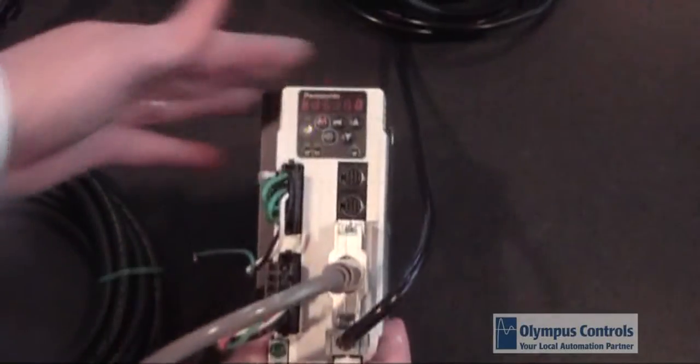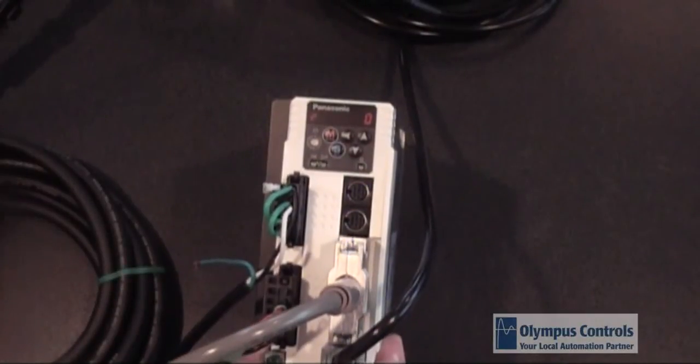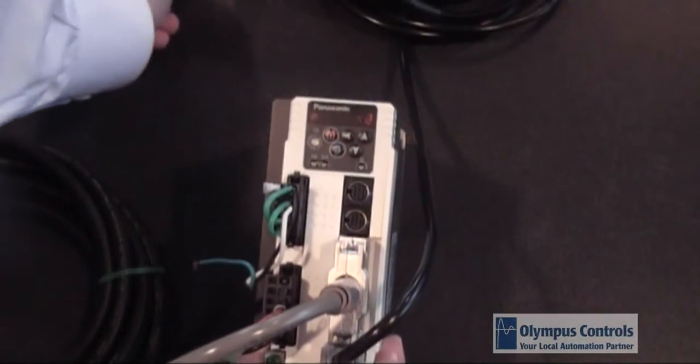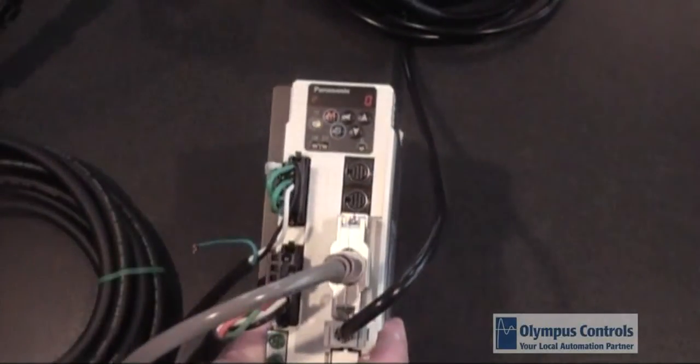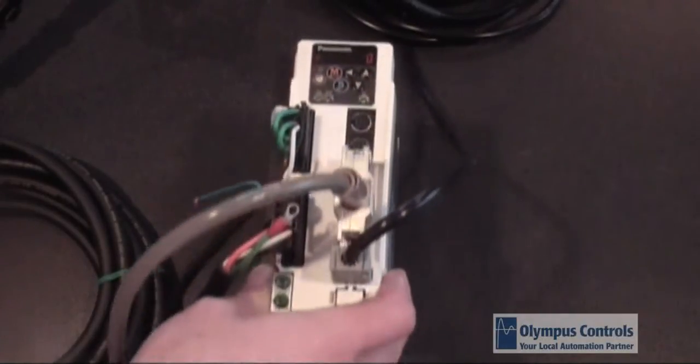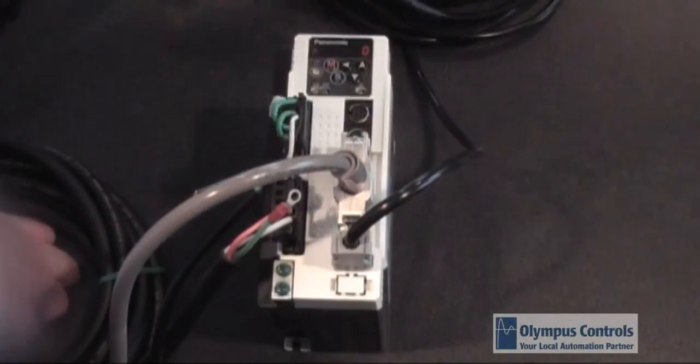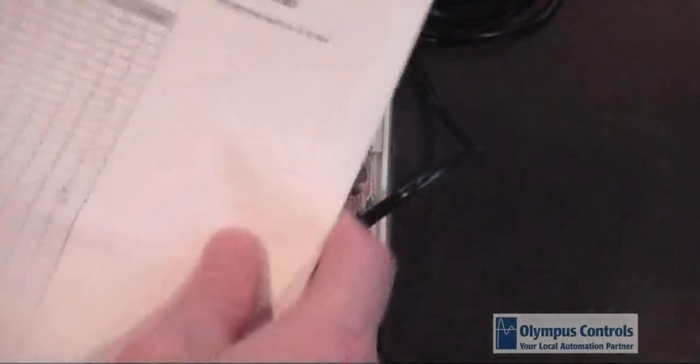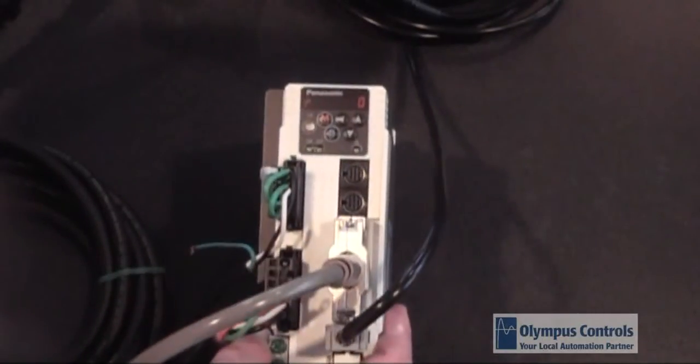Upon initialization, you'll see that it flashes on the screen and it comes up reading parameter zero. We're reading the display of the motor. If I turn the shaft, you'll see that the number changes. So I did not receive any errors, which means the axis is ready to run. The unit comes pre-configured as a side belt axis for the Austin tray wrapper. So if this was a side belt axis, it would simply be running and you would require no further action.